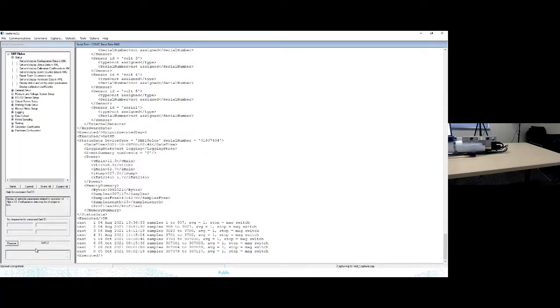Okay, so that is a pretty quick run through of SeaTerm V2. You can do a lot more with this. You can configure this instrument to work in Moored mode. And one of the more important things you can do with this is set it up to accept different auxiliary voltage sensors and log the data to memory. When you do that, you need to change the configuration file of your CTD, which we're going to demonstrate right now.